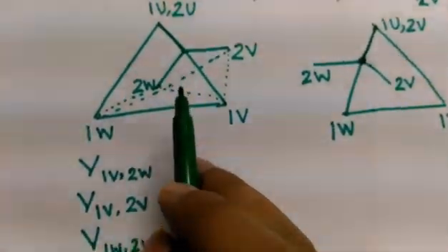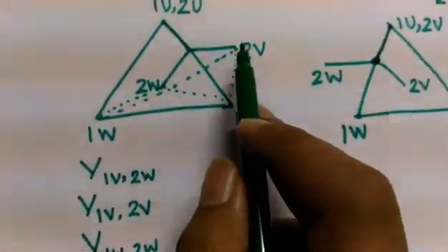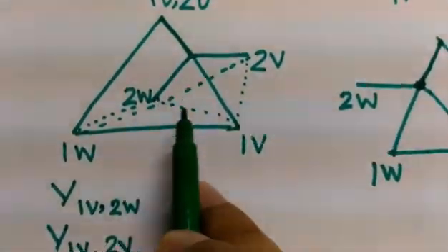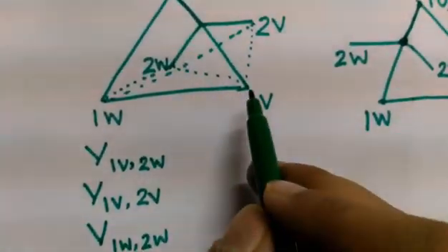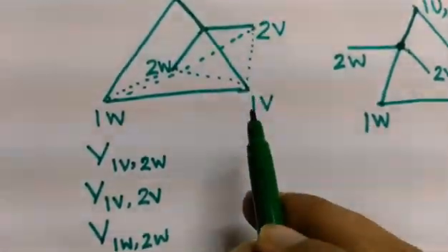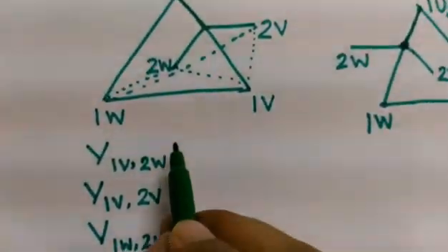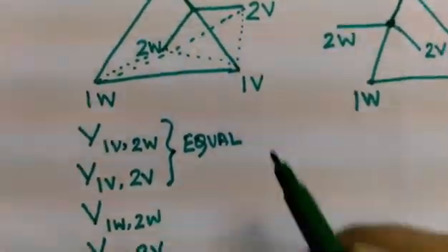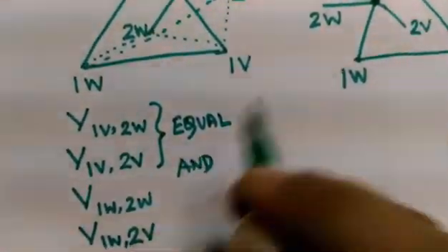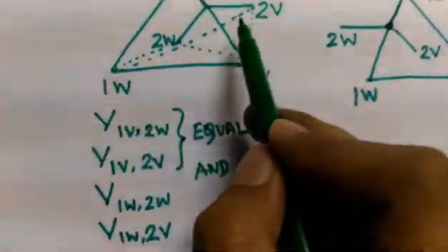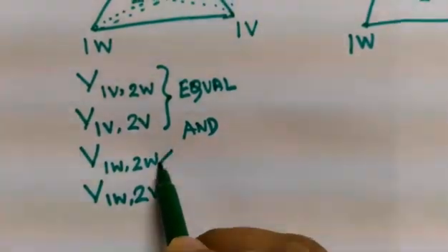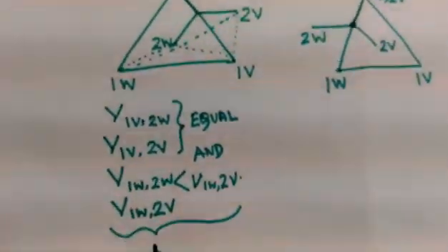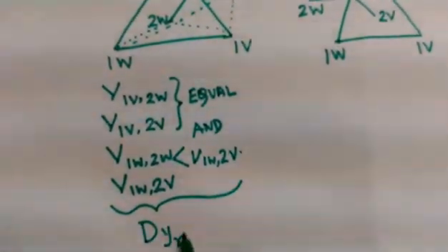If this is a Dyn11 transformer, you can see from the phasor that V(1V–2V) equals V(1V–2W) — these two voltages will be equal. And V(1W–2W) will be less than V(1W–2V). So if V(1V–2V) equals V(1V–2W), and V(1W–2W) is less than V(1W–2V), then you can conclude that this transformer is a Dyn11 transformer.